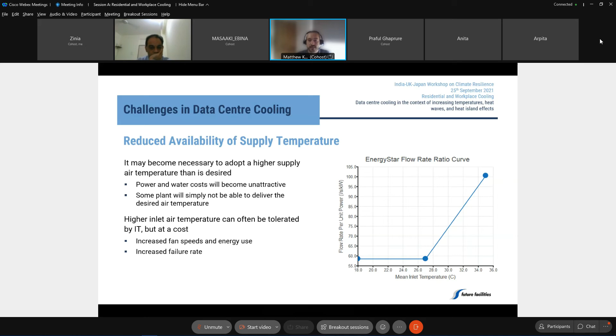But the higher inlet temperatures also lead to increasing IT equipment failures. Interestingly, there are actually some data centers in equatorial regions where they accept the trade-off of having a higher failure rate of their IT equipment in order to reduce their energy and water use. But at the moment that's relatively unusual, because it requires a very carefully designed IT system so that a failure can take place safely.